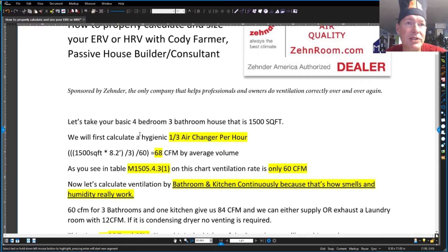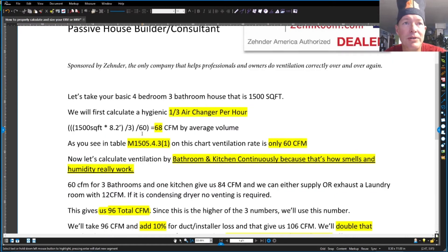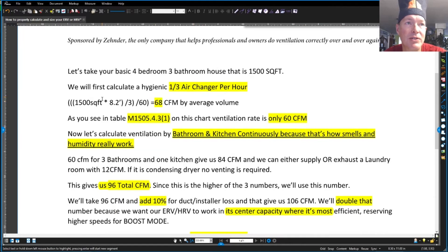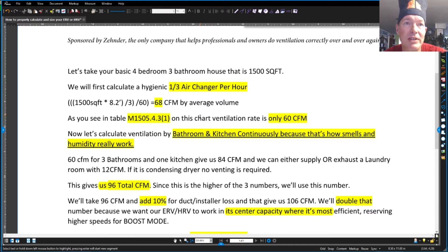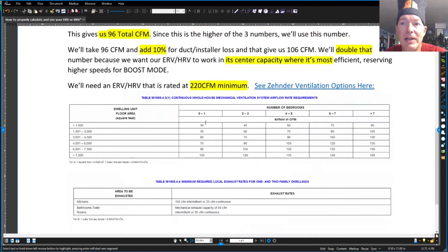So if we take a 1,500 square foot house — your average bread and butter, four bedroom, three bathroom — let's do that hygienic one-third air change per hour. 1,500 square feet times 8.2 feet tall, divided by three, divided by 60, and that's going to give you your total ventilation rate of 68 CFM. And as you'll see on M1505.4.3, that's right at 60 CFM for that 1,500 square foot.